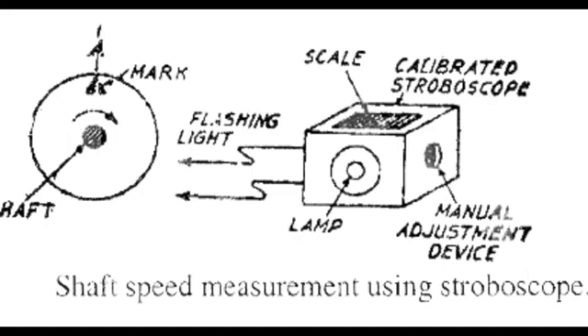To measure rotation speed, a mark is put on the surface — you can see the mark on screen — and the stroboscope light is flashed directly on the mark. The flashing frequency is adjusted until the mark appears stationary. At that condition, the speed is equal to the flashing frequency, as you can also see in this figure.